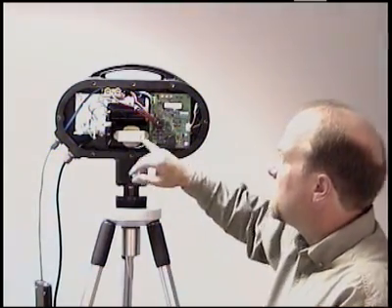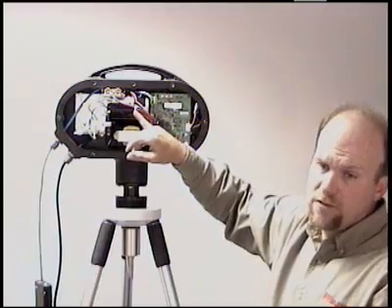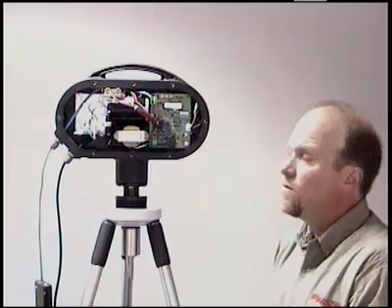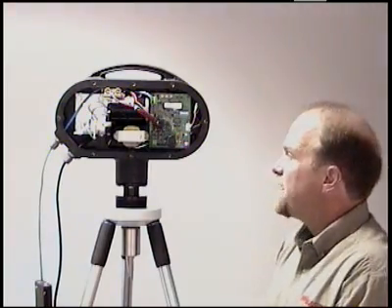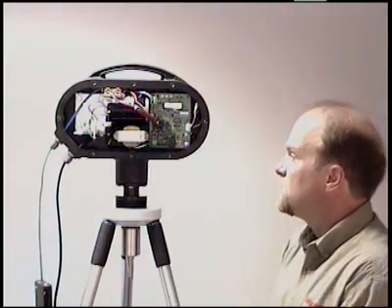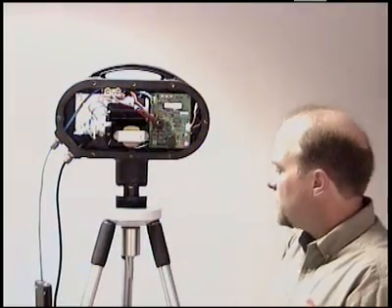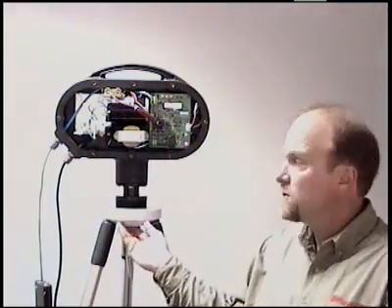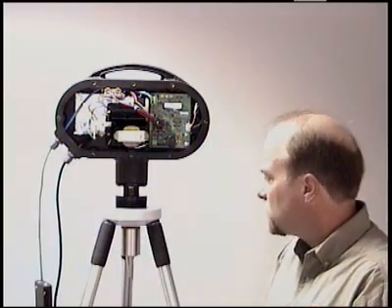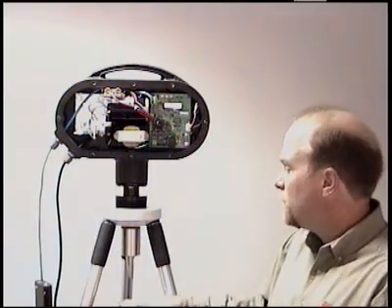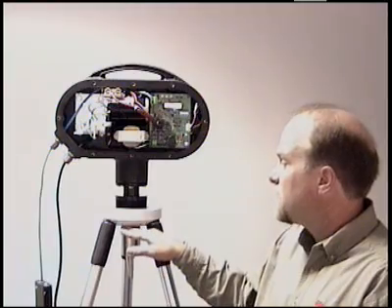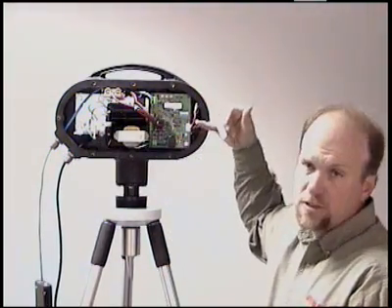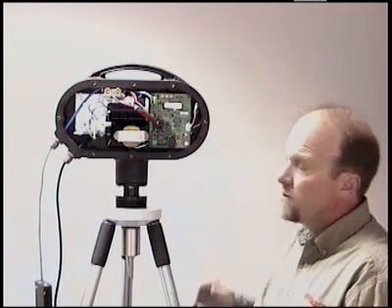We also have gone to a direct drive heavy duty reversible motor with electronic torque control to assure that we get full maximum power throughout the measurement cycle. The way that we get a soft touch so that it doesn't come up and slam into this flange is we control the torque. We work at the top 12 inches of the retract cycle so that we can protect the gears and the components within the PC board.